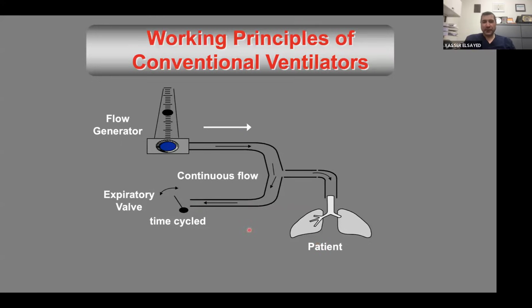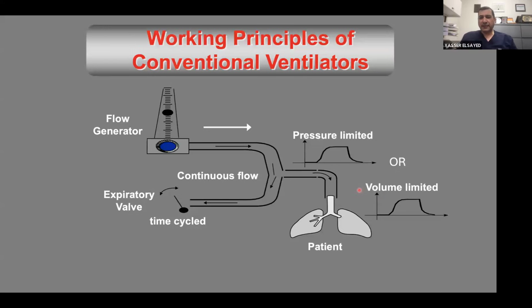So what we need to know is how much flow we are applying, and through this flow, the machine can adjust or calibrate a tidal volume and the pressure. And we have the time cycle valve here. So we have the pressure limited, and also we have the volume limited. As we'll explain later, what we are using in the NICU is pressure limited. It can be hybrid with the volume, but we are not using volume limited. It is mainly for adults.